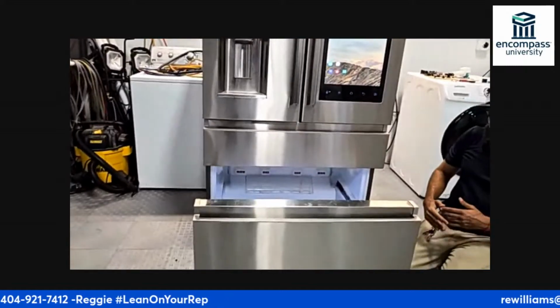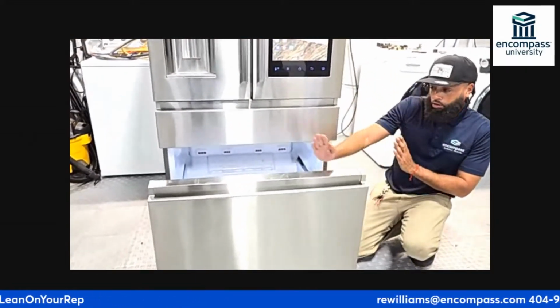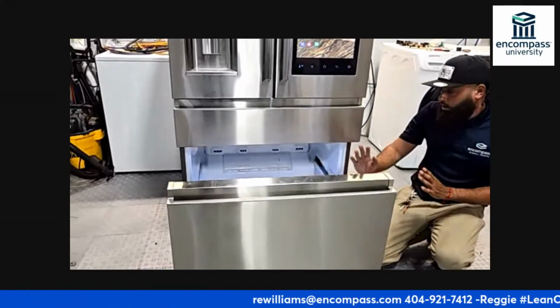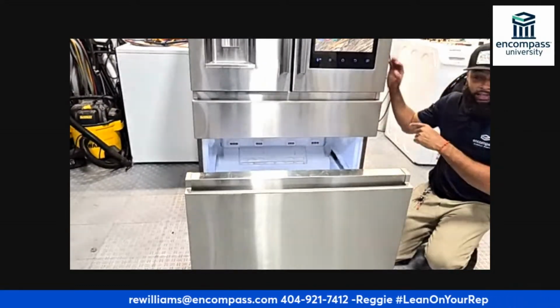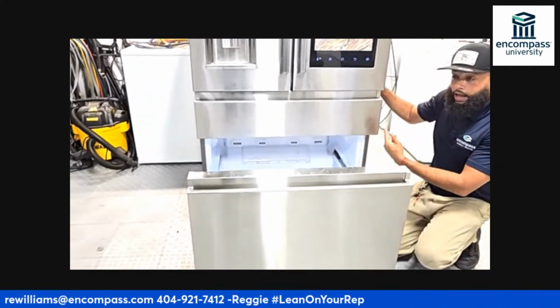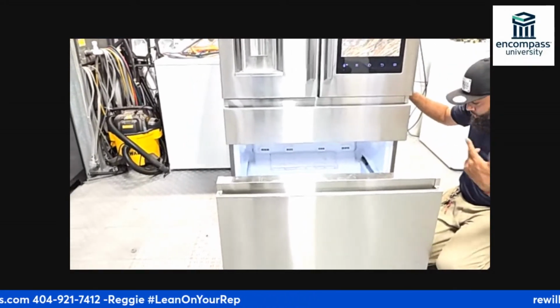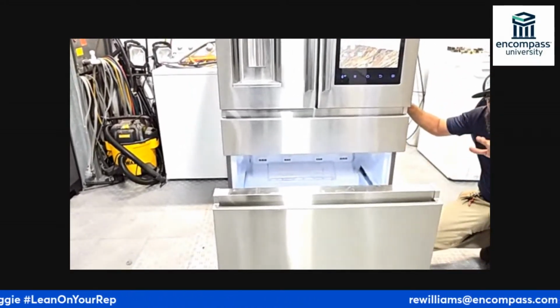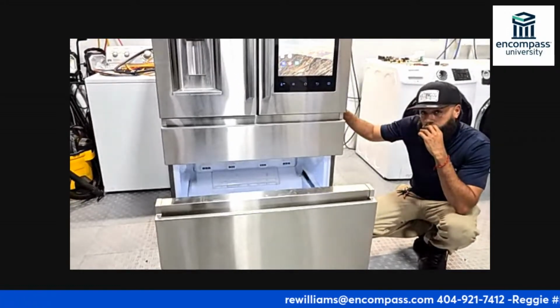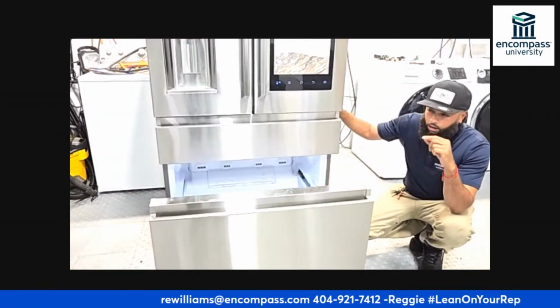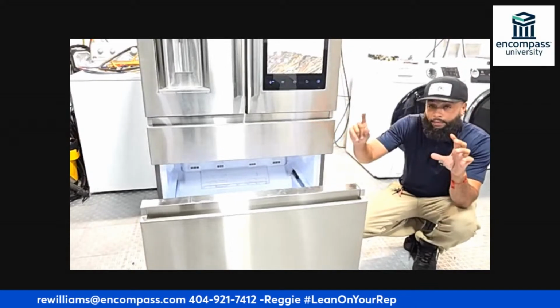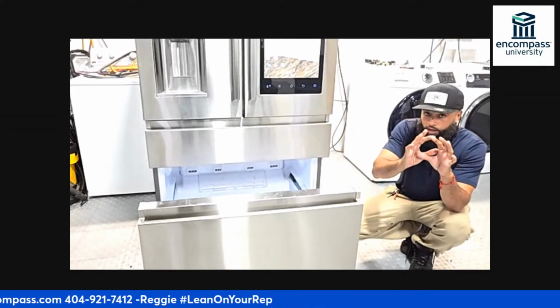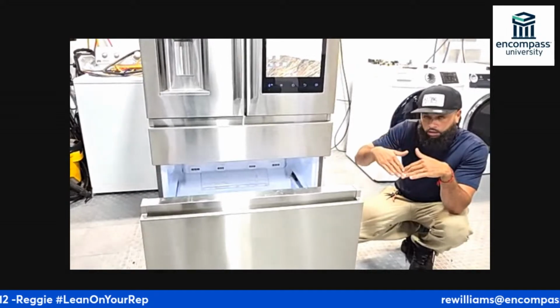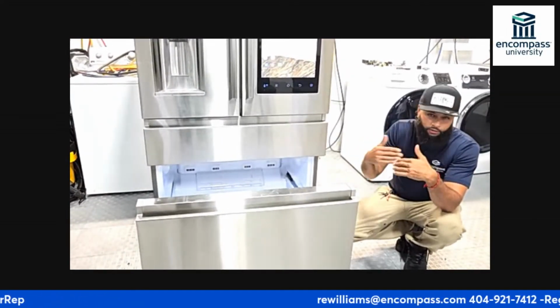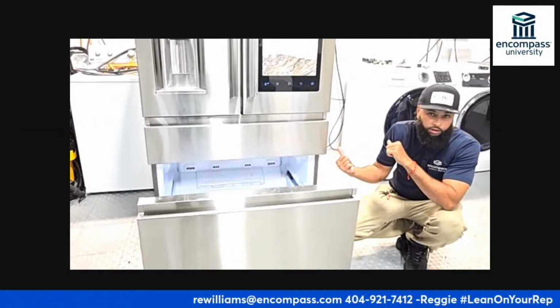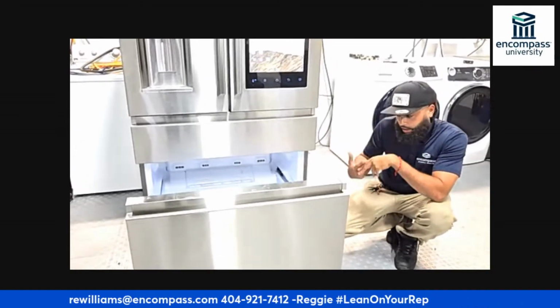Another thing I want to do is make sure my door gaskets are all good. These fans won't activate when the lights are on, so you may have to trick the fridge and press the door switch. On certain models, they don't have door switches, they have reed switches, where you take a magnet and stick it to that switch, and that triggers the lights to turn off. After 7 to 12 seconds, you hear your evaporator fan kick on.